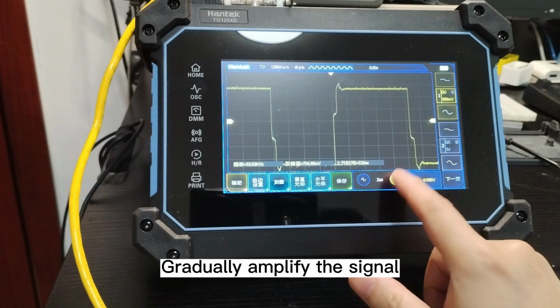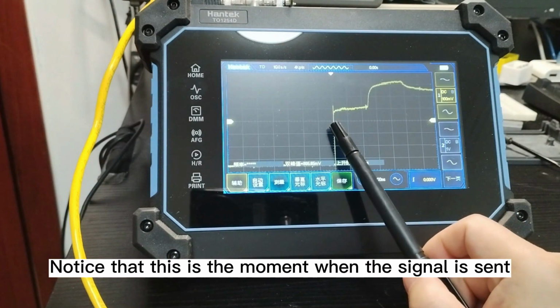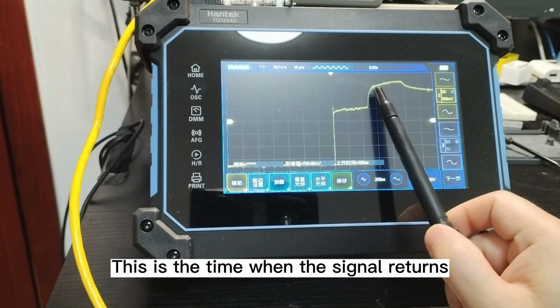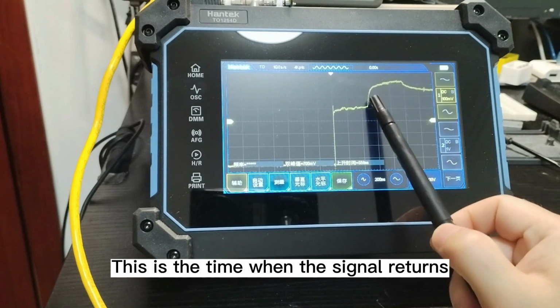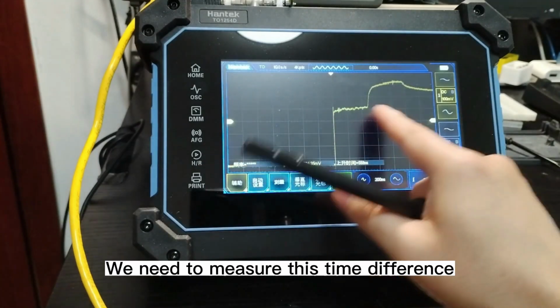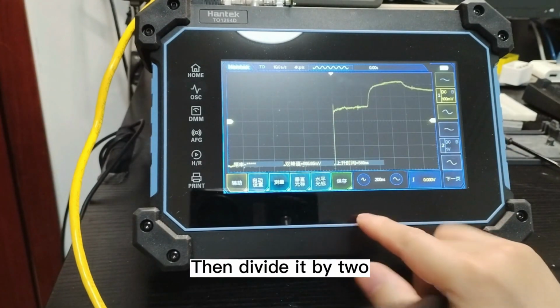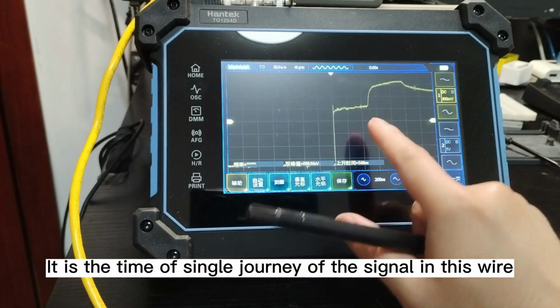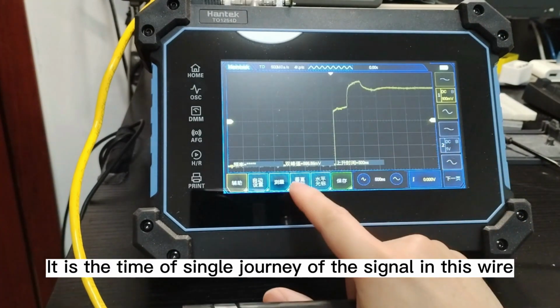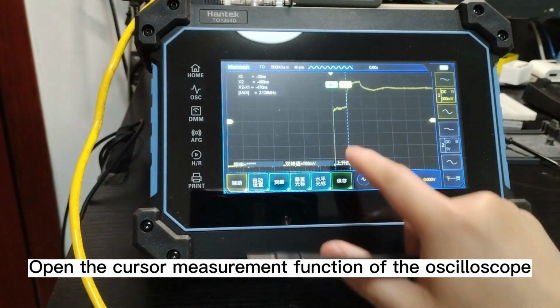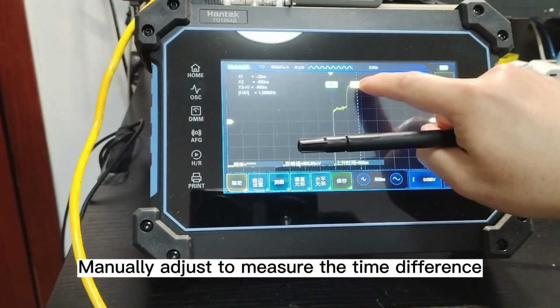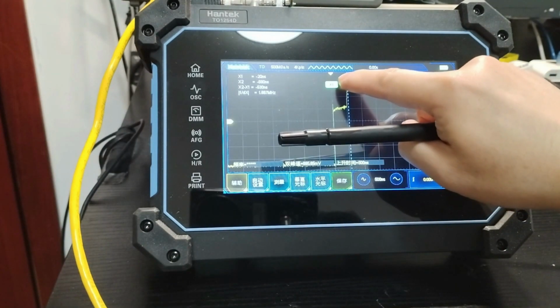Gradually amplify the signal. Notice that this is the moment when the signal is sent. This is the time when the signal returns. We need to measure this time difference, then divide it by 2. It is the time of a single journey of the signal in this wire. Open the cursor measurement function of the oscilloscope. Manually adjust to measure the time difference.